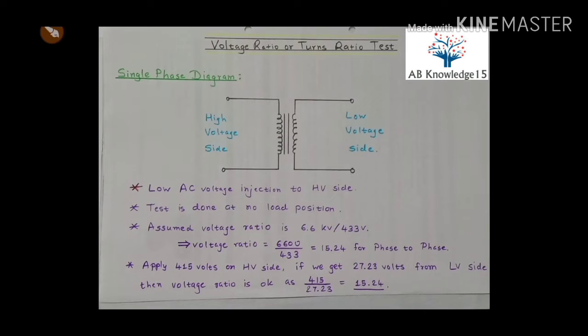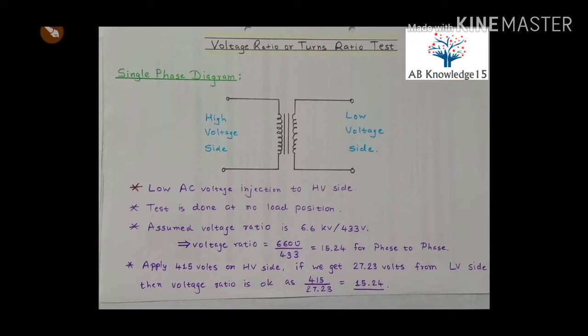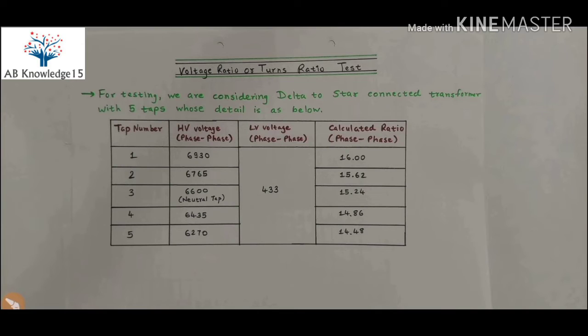This test is done at no load position of transformer. Now assume that voltage ratio is 6.6 kV to 433 volts. Voltage ratio will be 6600 to 433, which is 15.24 for phase to phase voltage. So if we apply 415 volts on HV side and if we are getting 27.23 volts from LV side, then voltage ratio is ok as the division of 415 to 27.23 will be 15.24.